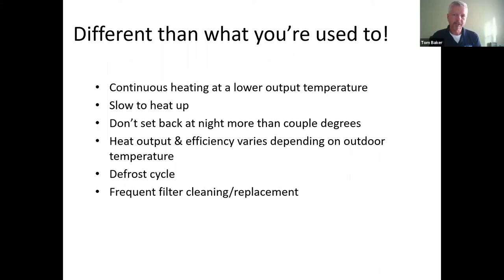Okay, first part of the question, the difference between a thermostat for a mini split and a traditional system is the mini split system has a lot more control over how the system runs because the technology in the heat pump outside is called an inverter. It's an inverter compressor, which means it's infinitely variable in terms of the output. Let's say that we put a 36,000 BTU unit outside. In a traditional heat pump, every time it comes on, it's going to be delivering 36,000 BTUs into your home. Whether it's 50 degrees outside or 20 degrees outside, it comes on at full speed.